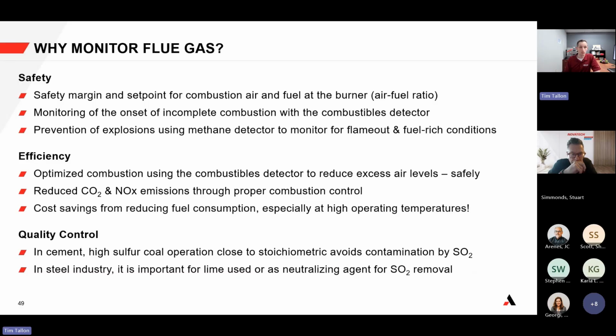So that's something I think about. It's really important. I'll go into that in a little more detail in just a second, but that's something I think about when it comes to the methane detector. A lot of people wonder, okay, carbon monoxide and hydrogen are combustible, so why is methane not included in a combustible detector? There are some nuances of the technology, but to get a good measurement for carbon monoxide and hydrogen, things that are incomplete combustion, it really helps to have a separate detector for combustibles and a separate detector for methane. All that said, keeping them separate allows you to monitor for safety at different levels: safety at the combustion air side, safety at the combustible breakthrough side, and also safety for a hydrocarbon flame out type of scenario.